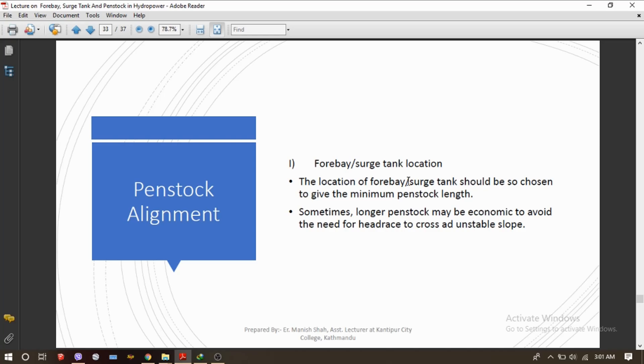Now let's talk about penstock alignment, starting with forebay and surge tank location. The location of the forebay or surge tank should be chosen to give the minimum penstock length. If the surge tank is placed nearer to the powerhouse, the length of penstock is automatically minimized. However, sometimes a longer penstock may be more economical to avoid the need for a headrace to cross an unstable slope.